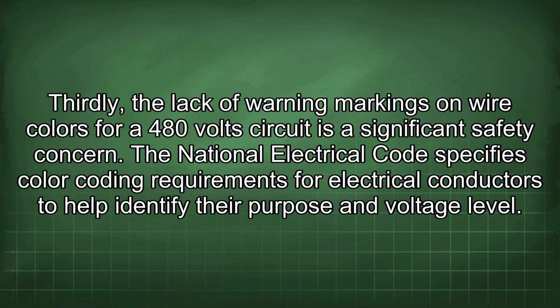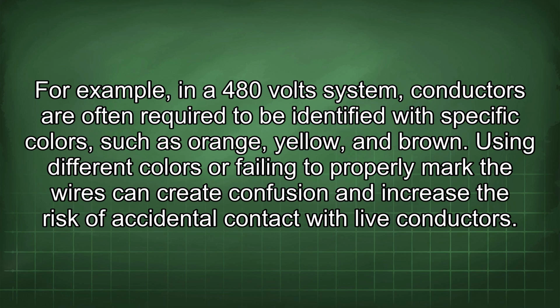Thirdly, the lack of warning markings on wire colors for a 480-volt circuit is a significant safety concern. The National Electrical Code specifies color coding requirements for electrical conductors to help identify their purpose and voltage level. For example, in a 480-volt system, conductors are often required to be identified with specific colors, such as orange, yellow, and brown. Using different colors or failing to properly mark the wires can create confusion and increase the risk of accidental contact with live conductors.